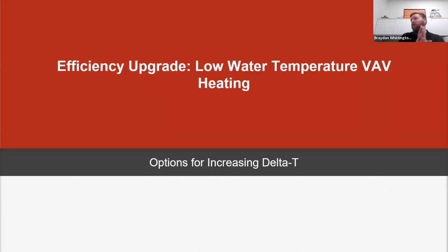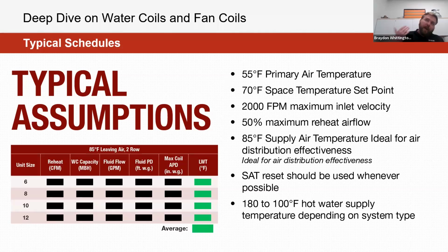Now we're going to look at some of the different options that you have available for your utilization, and we'll look at a case study as an example as well. So first off, let's look at some of the options for increasing our delta T at a water coil level. A good way to highlight this is taking it back to a terminal level for comparison, but this is applicable to standalone coils as well as coils that might be paired with fan-powered equipment. On screen here, I've just put this up as an example of where this comparison comes into play. Here are some typical assumptions that we're laying out for these single ducts before we go through what some of these different options are.